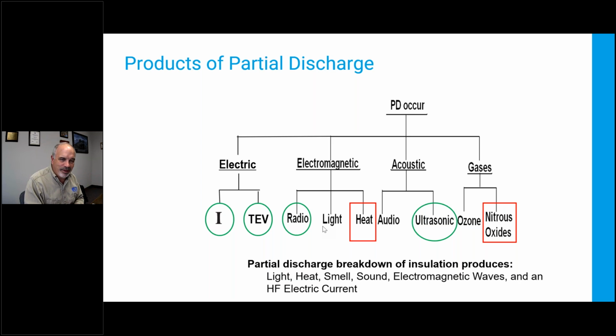Moving back over to the left, the electric phenomenon, we have current. We said PD is a current. If I can measure that current directly, that's fantastic. And the other thing is TEV, or transient earth voltage. And this is a voltage that is induced on a grounded metal enclosure, say metal-clad switchgear, shield on a cable, things like that, tank on a transformer, due to discharge inside. And if we can detect that voltage non-contact from the outside, we've got a much safer way of finding PD. So that's kind of the breakdown of what happens with partial discharge and what's good and what's bad about it.